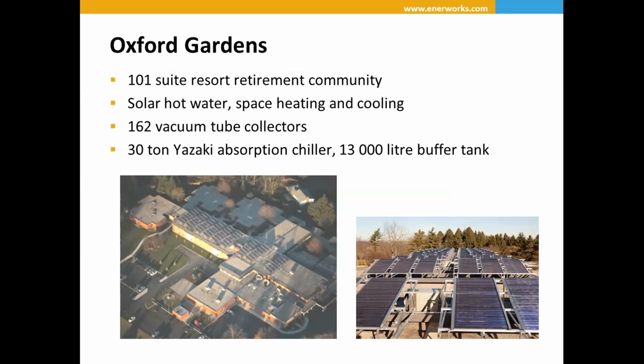And in the winter months, there's a pool there. We add the heat to the building heating loop, domestic water, and the pool. So we were able to shave off, I think it was 70,000 kilowatts of electricity used for the chillers, and in the winter shave their natural gas consumption pretty significantly. And this is a nice load because in the summer we've got the absorption chiller, so we can add that heat in the winter, so it's a fairly balanced load.